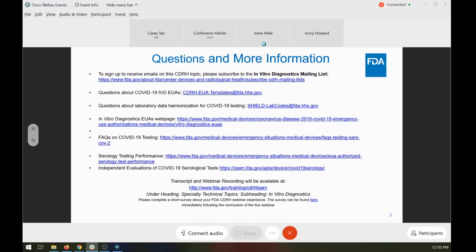Yeah, I mean, we are covering 809.10 in the paper insert, and in terms of the IVD regulations in general for lab products, those are not lay user. For professional user purposes, paper package insert is not required. Electronic package insert is acceptable. What I'm specifically asking for is for home users or non-lab users, layperson kind of environment. That's the key distinction. Otherwise, the elements are there. Okay, sure. So if you can send that in, that's something that we can take a closer look at in your proposal. Okay, great. Thanks so much. Sure.